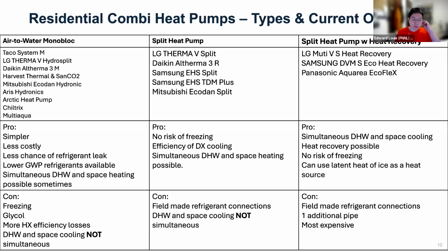And then some of the pros and cons of the different systems. With the monoblock system, the main pro is lower refrigerant charges and less chance of a refrigerant leak, because there are no field-made connections. The other two columns to the right of that, those systems require field-made refrigerant connections. So you'd really need a workforce that is good at making those connections, pressure testing, and vacuum decay testing, so that those connections are solid.